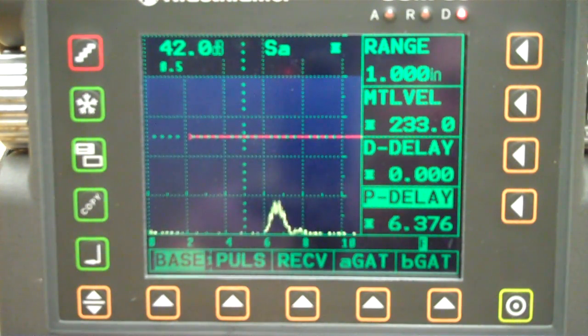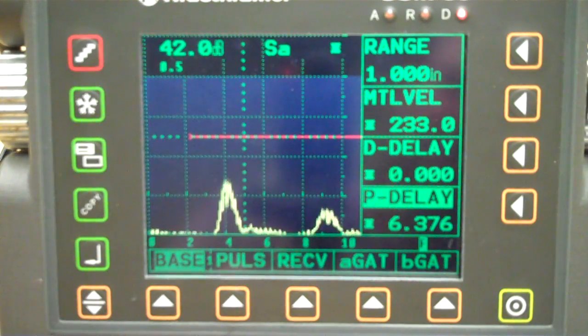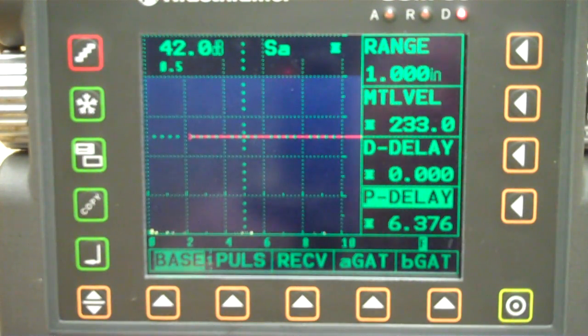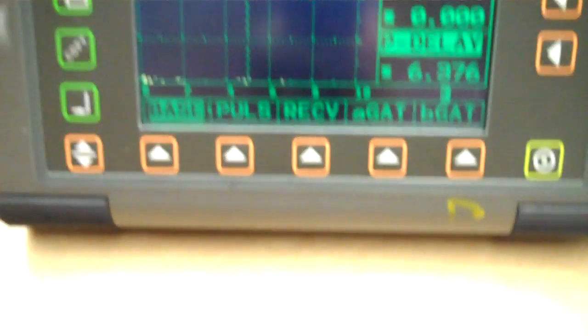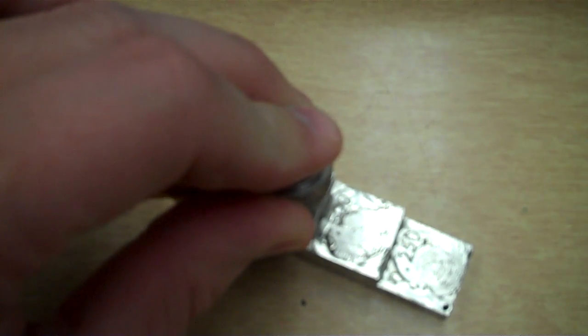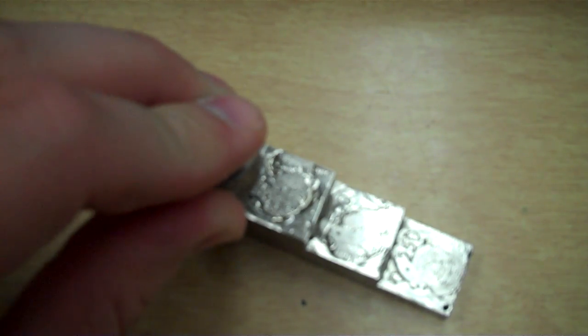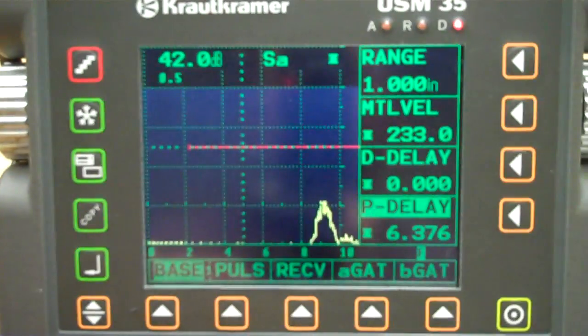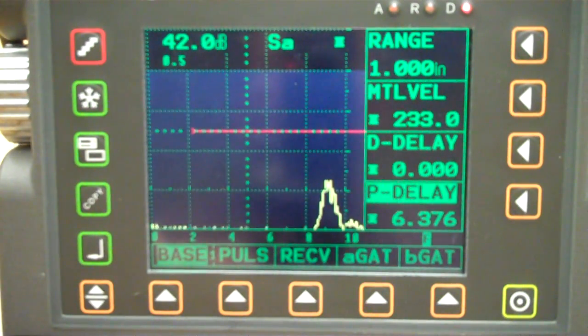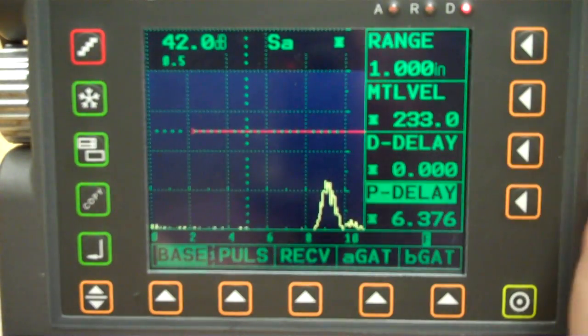Now with the dual element, this signal may not be the prettiest, but it's going to work alright for telling us thickness. So we've stretched this out. Let's get a whole view here and see if we can see. There's 1/4 inch, 1/2 inch, 3/4 inch, 1 inch. So there's our 1-inch signal. We know we're not in the right spot. We're on a 1-inch range.